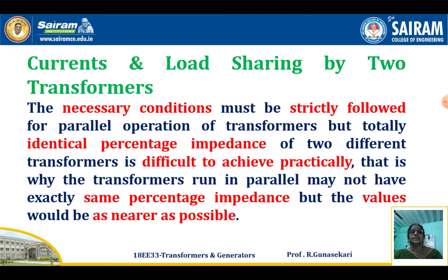The necessary conditions are: same polarity, same percentage impedance, same phase sequence for a three-phase transformer, same vector group for a three-phase transformer, same voltage and turns ratio, same frequency, and then same kVA rating. This last one is optional only; transformers of different kVA rating can also be connected in parallel.